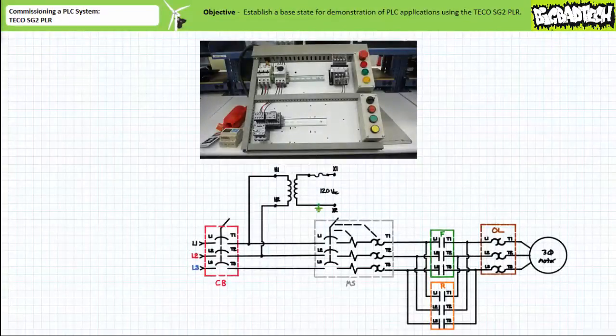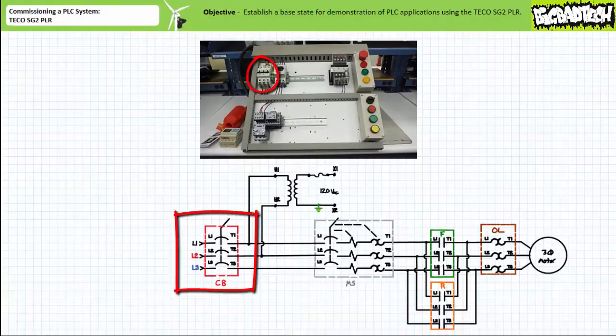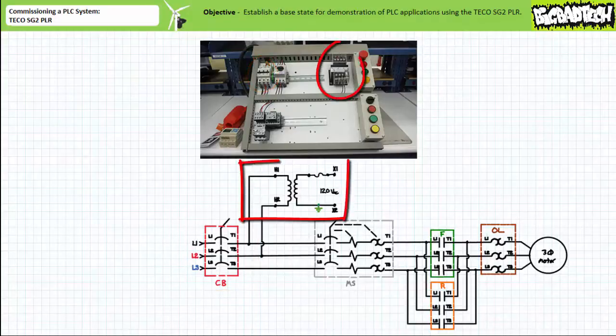We'll initiate this application exercise with primary devices configured in the following fashion. A main circuit breaker makes and breaks connection to light industrial 120 volt line to neutral, 208 volt line to line, 60 Hz, 3-phase AC. Immediately downstream of the circuit breaker, a control transformer steps down the 208 volt line-to-line voltage to our chosen level of pilot level voltage, 120 volts AC. The X2 side of the control transformer is ground referenced.